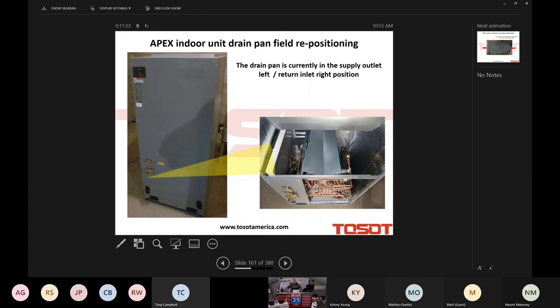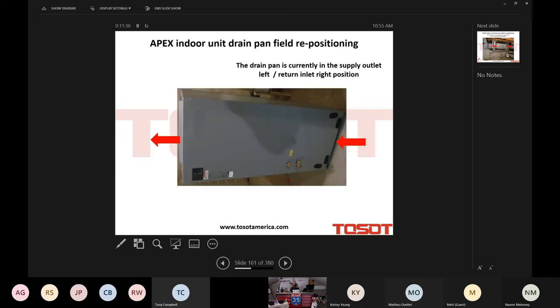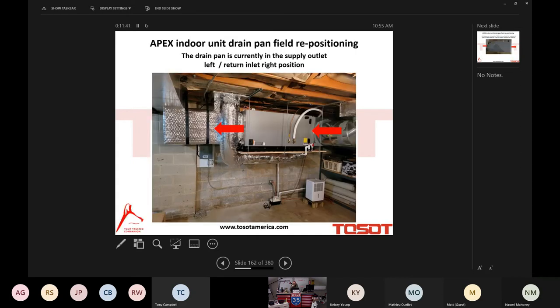Repositioning of that pan when we go to the horizontal position. See, out of the factory, the drain pan is currently set for supply outlet left and return inlet right. So if you're doing this, which is what I did, no need to reposition the pan. And there you go, there's a great visual of the mechanical room here in the house in Pennsylvania. Again, I didn't have to reposition the pan because it is from the factory ready for this application, supply outlet left, return inlet right.